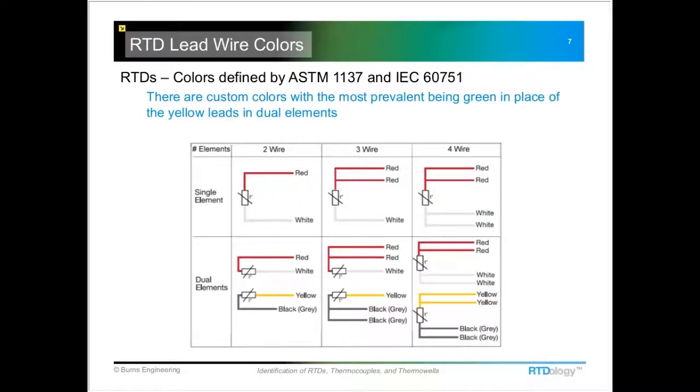Now there are some differences in the color coding based on manufacturers. The standards define the colors as this, but there are at least two or three manufacturers that substitute green for the yellow leads, especially on the dual elements. So that's where you're going to see kind of the biggest difference. These will just be green. For several of the big instrument houses, we'll use a different color code there.